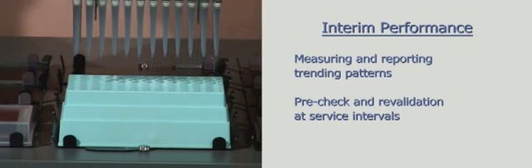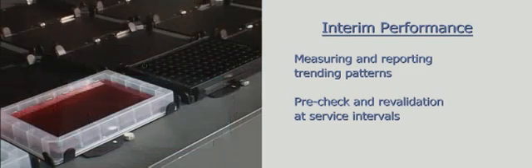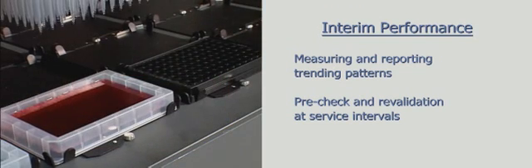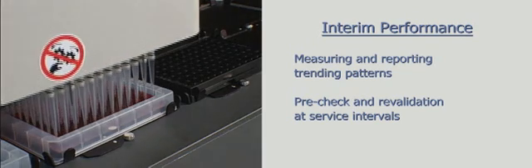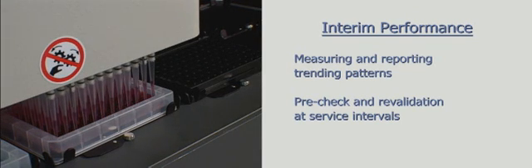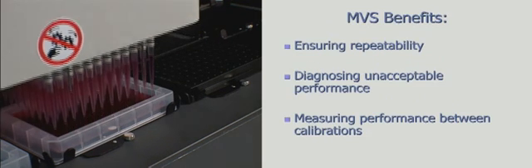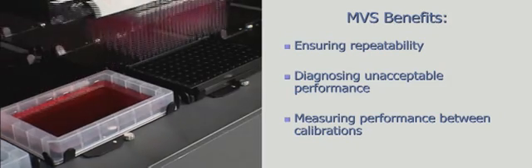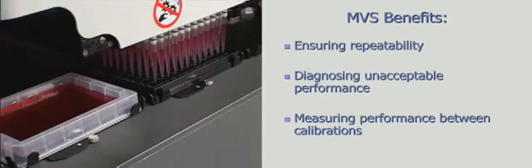The MVS can be employed to show dispense-trending patterns of the liquid handler between preventive maintenance calibration intervals. The MVS can also be used to measure performance of the instrument before and after the manufacturer's service, ensuring dispense repeatability even after changes to the system have been made as part of the maintenance or calibration procedure.